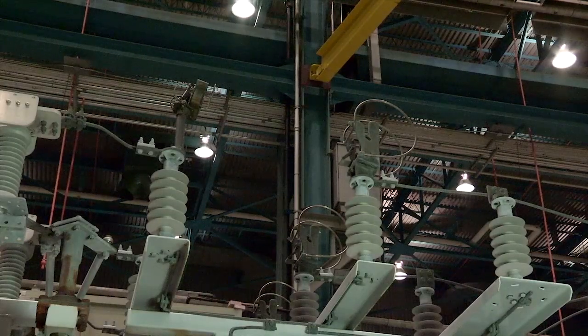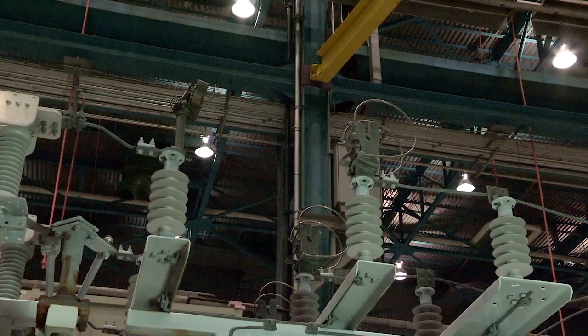Next, we're looking at the high voltage fuses. A good thing to do is obviously overhaul them, clean them up, grease them, but also to do a dry run with an actual fuse just to make sure it pops up and out and not staying in there and everything's mating correctly. And as you're going along too, just make sure that all bus and everything's tight and torqued and connected, because these things rattling down the road, everything seems to loosen off quite a bit.